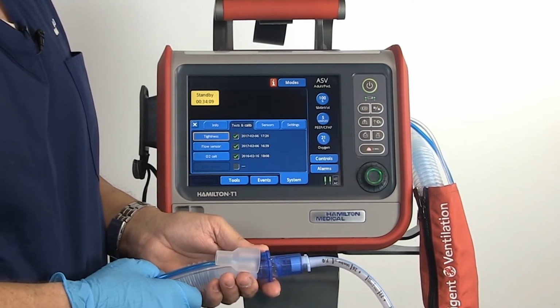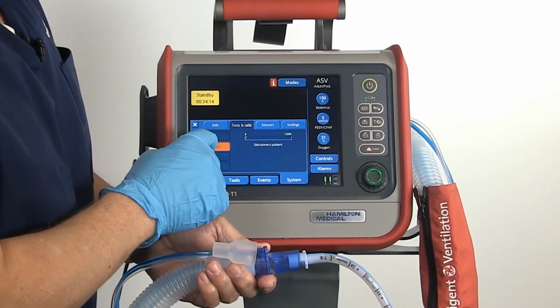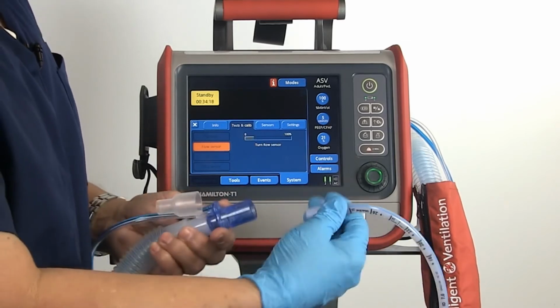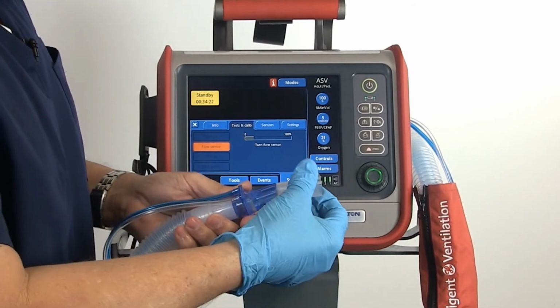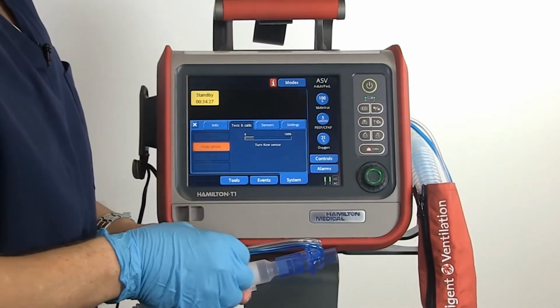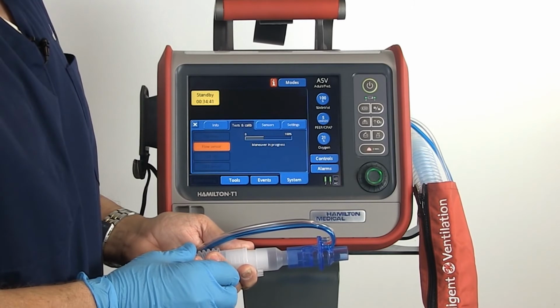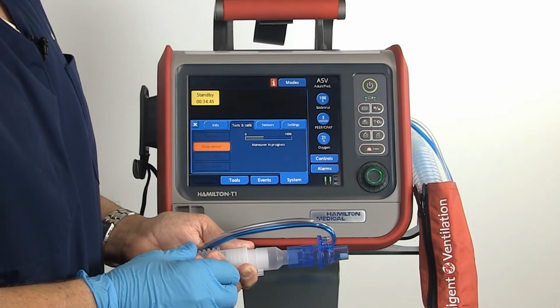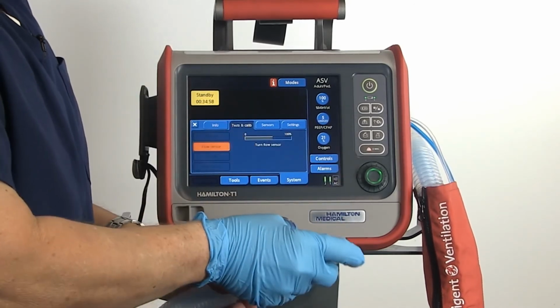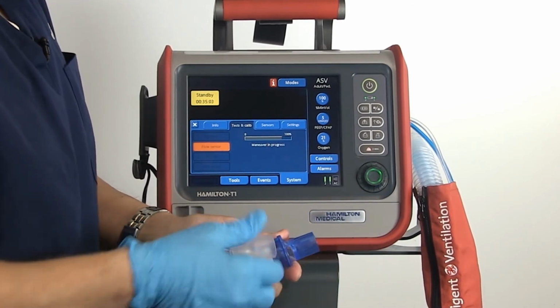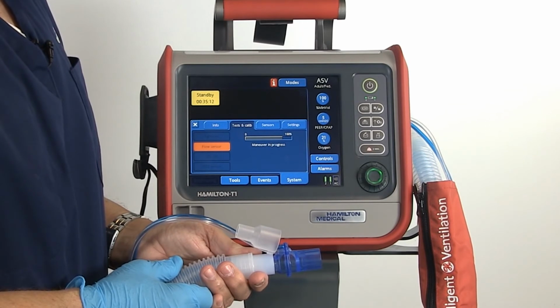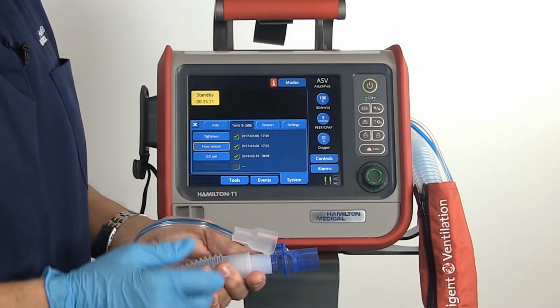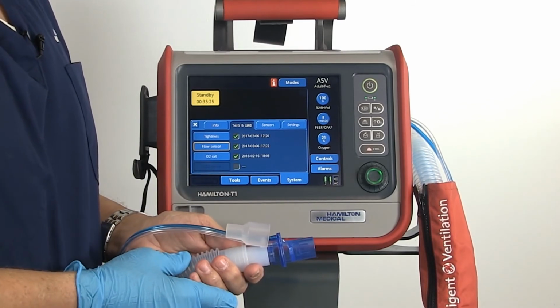Our next test will be for the flow sensor. So you press the tab. You've got a connector on your flow sensor. Take the connector off and turn the flow sensor as indicated by the screen. The flows will slowly ramp up. The command says to turn the flow sensor again, so we will turn it, remove the connector, and replace it onto the circuit. Once again, we get the indication with the green check that the pre-ops are complete.